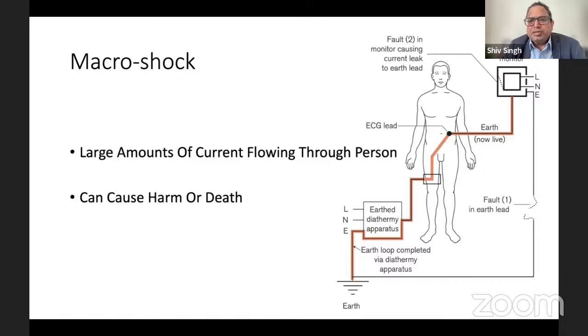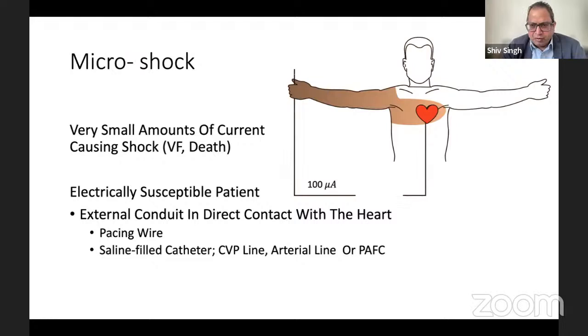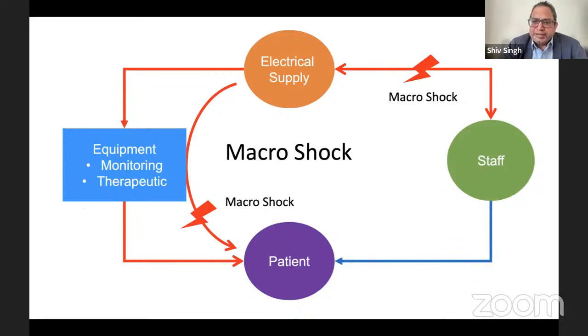A large amount of current can flow through a patient or through us only if we directly touch a faulty equipment. Whereas with micro shock, like I said, you need a current of almost 100 to 150 microamps, usually more than 50 microamps and at least 100 microamps to cause VF. So we'll look at macro shock. How does it actually happen? It's no rocket science. If you have a faulty equipment, for example, a faulty toaster, you touch it, and you feel a tingling sensation, or you feel like current flowing through you, that's a macro shock. It may not have killed you, but you felt it. That's macro shock.